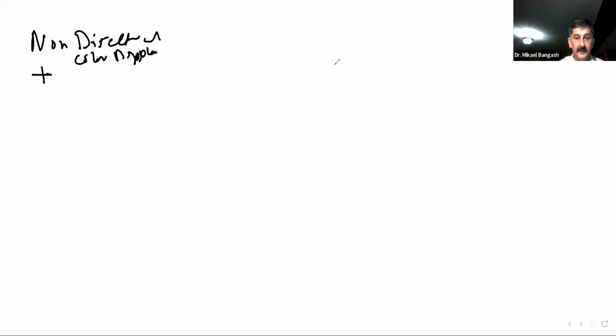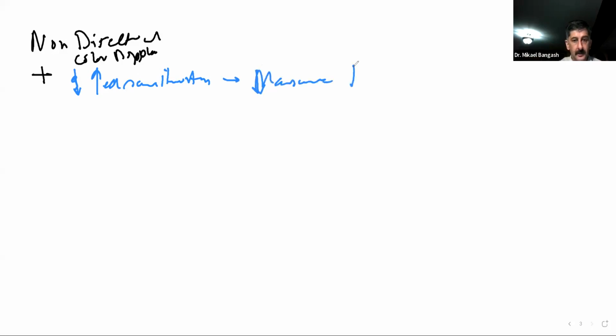One of its main advantages as well is that it has an increased sensitivity. And what did that increased sensitivity enable it to do? Measure low velocities, which we already said means fine flow. So it enables our ability to measure low velocities.